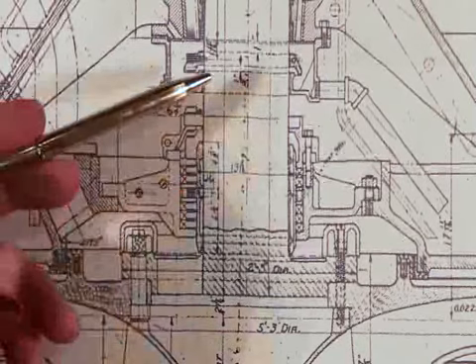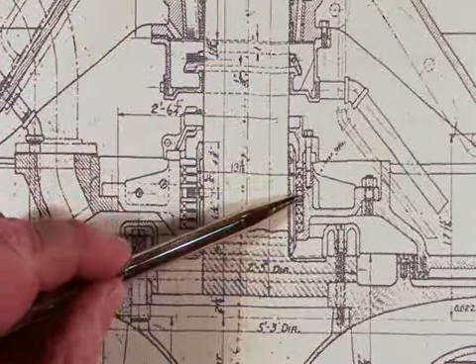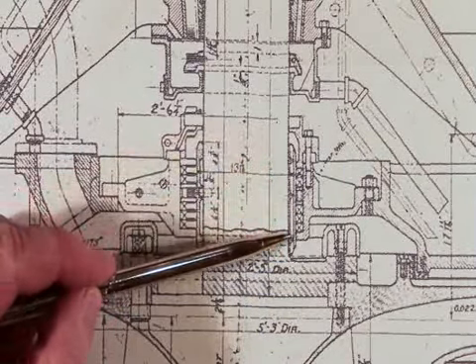Below the main guide bearing, this stuffing box was packed with 5 rings of braided packing and a lantern ring. The role of the packing was to prevent any oil from leaking downward and to keep water from entering the powerhouse. The packing runs against a replaceable shaft sleeve.